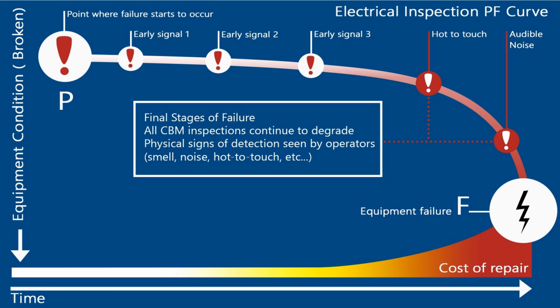So looking at the PF curve, doing something when you find these early conditions and having an action plan in place - if you reach a critical temperature measurement, or you hear a dB level, or you see a current or voltage measurement that exceeds an agreed alarm level, you can do the repairs before you get to these stages where the equipment's been enabled to run in these failure modes for too long.